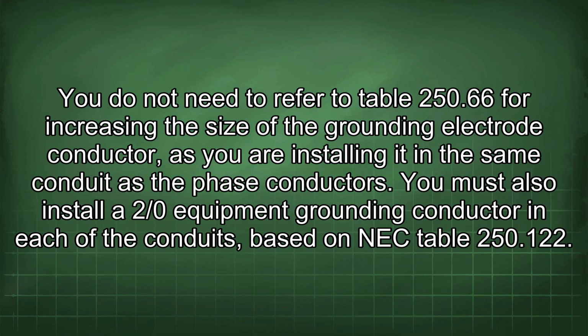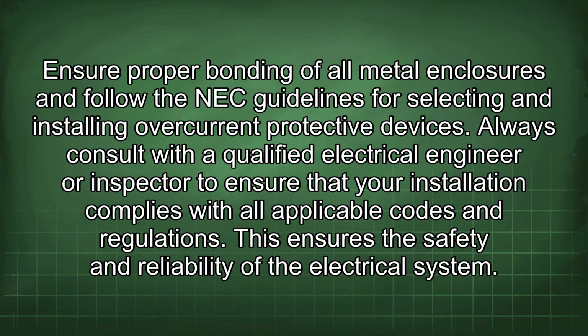You must also install a 2/0 equipment grounding conductor in each of the conduits based on NEC Table 250.122. Ensure proper bonding of all metal enclosures and follow the NEC guidelines for selecting and installing overcurrent protective devices. Always consult with a qualified electrical engineer or inspector to ensure that your installation complies with all applicable codes and regulations. This ensures the safety and reliability of the electrical system.